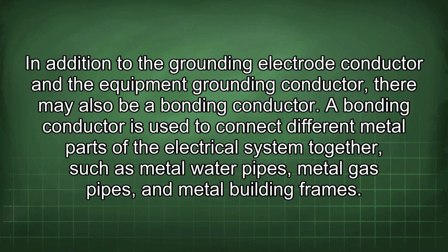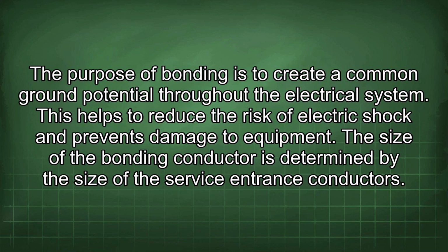In addition to the grounding electrode conductor and the equipment grounding conductor, there may also be a bonding conductor. A bonding conductor is used to connect different metal parts of the electrical system together, such as metal water pipes, metal gas pipes, and metal building frames. The purpose of bonding is to create a common ground potential throughout the electrical system. This helps to reduce the risk of electric shock and prevents damage to equipment.